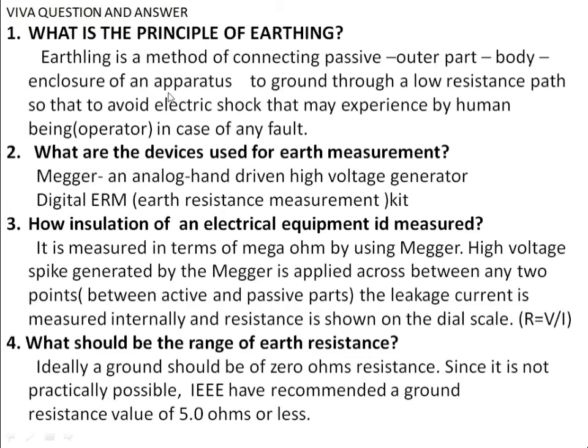So now let us see the viva questions and answers. The first question is, what is the principle of earthing? We already discussed. Earthing is a method of connecting the passive outer body or enclosure of an apparatus to ground through a low resistance path, so as to avoid electric shock that may be experienced by a human being, the operator, in case of any fault. What are the devices used for earth measurement? Megger and digital earth resistance measurement kit. Megger is an analog device, and the digital ERM, earth resistance meter, is a digital device.